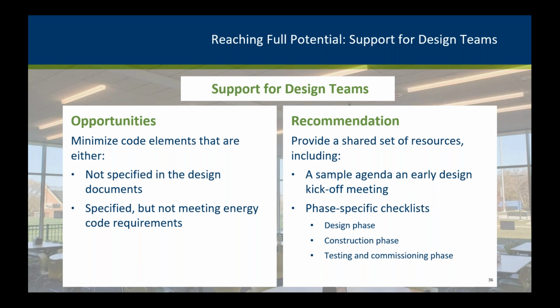Our study also found that design team support can help increase energy savings by minimizing the number of code elements that are either not specified in the design documents or specified but not meeting energy code requirements. So this would start with making sure that the different code pathways are understood and specified on the documents. As Jeanette alluded to, 33 of the 78 projects in our study did not indicate whether IECC or ASHRAE was used as the code pathway. But support should also be provided for the code elements that Tinyao called out as being commonly missed or misunderstood, whether that's thermostat deadband, the receptacle controls, things like fenestration orientation as well.